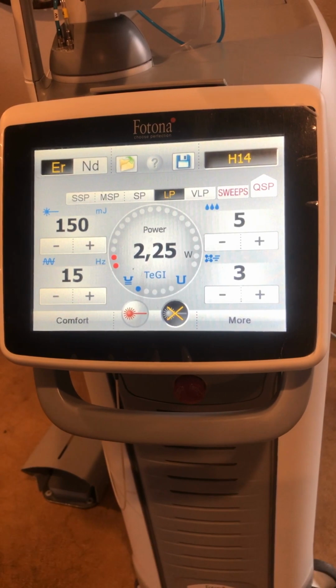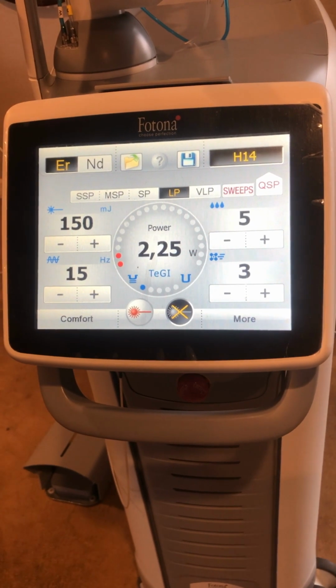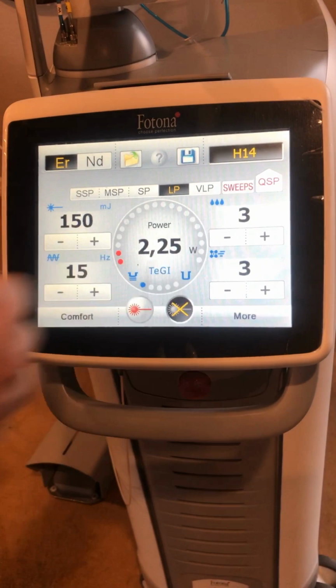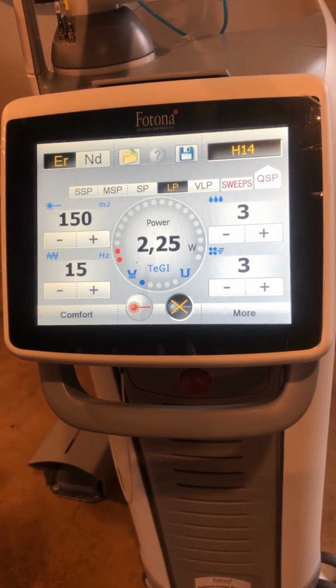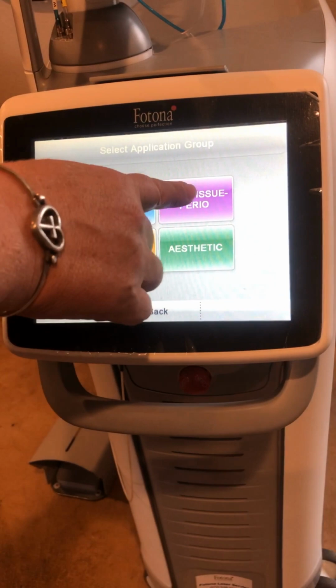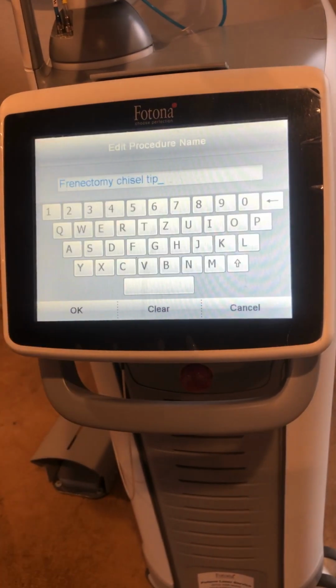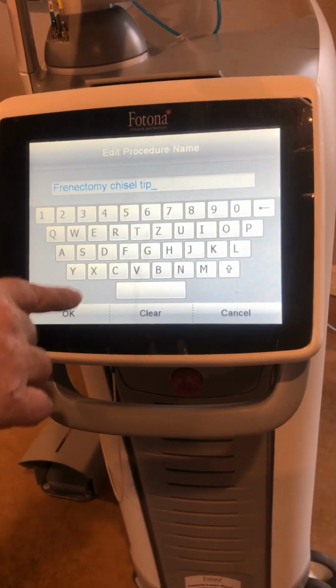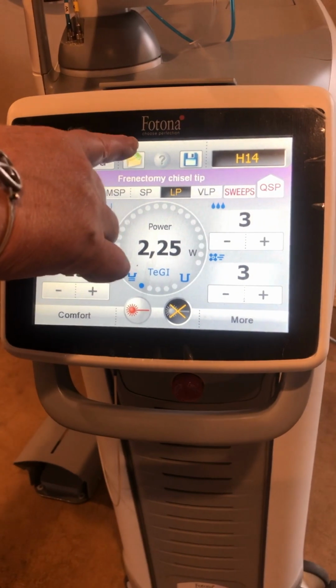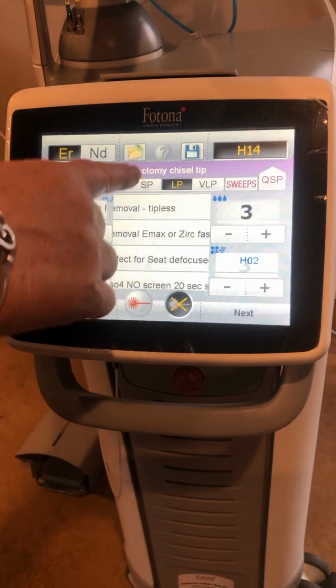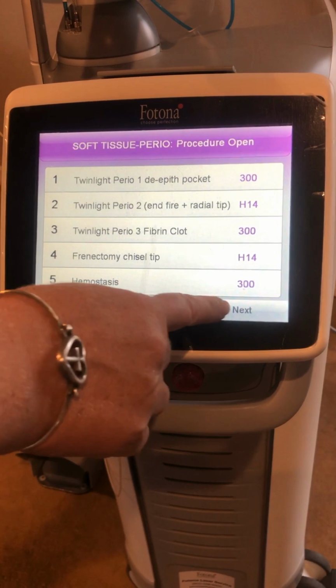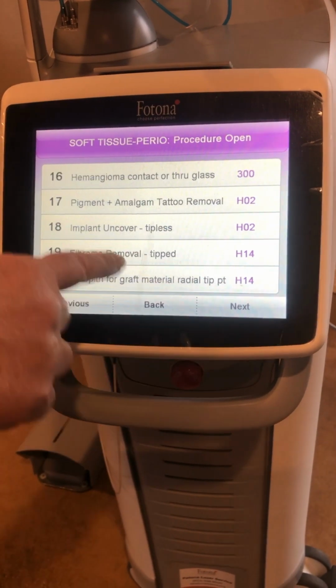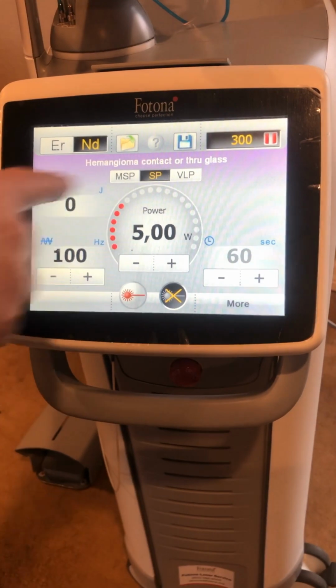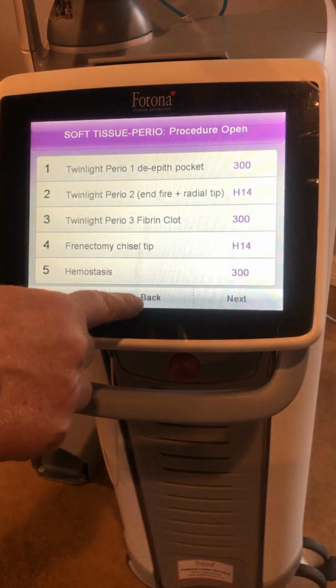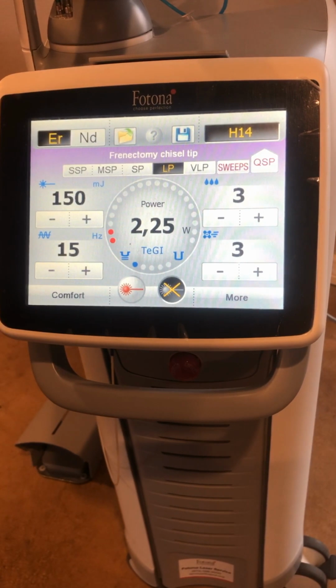I want the millijoules to be 150, and I want the hertz to be 15, which is perfect. I want the water just to be 3, and I want the air to be 3. And so now that I've made all those changes, I'm going to hit the save button. Okay. Then I'm going to go into the category that I know I'm going to put this in, and I'm going to click the spot where I want to save it, change the name to whatever it is that I want to save, and then hit OK. And now if I go back into this category, and I go to that area where I just put that in, now if I click on hemangioma, it's the setting that I just saved a minute ago. Or if I go back in and I click on the frenectomy one I just saved, it has changed to the presets that I want.